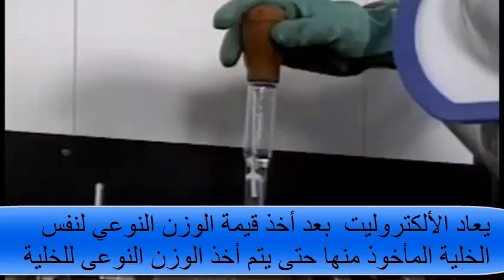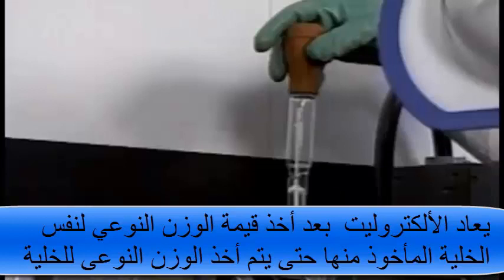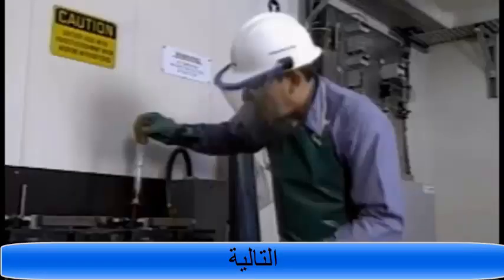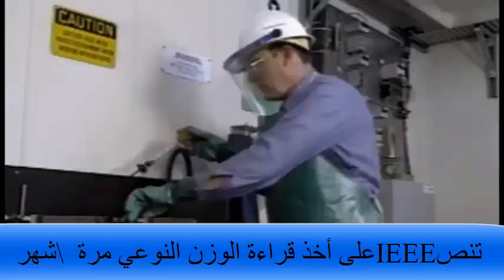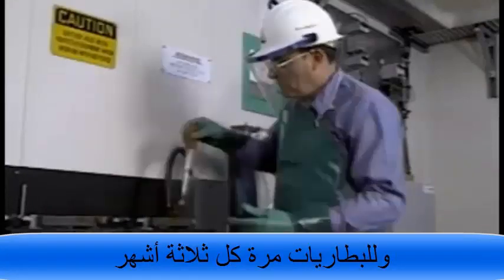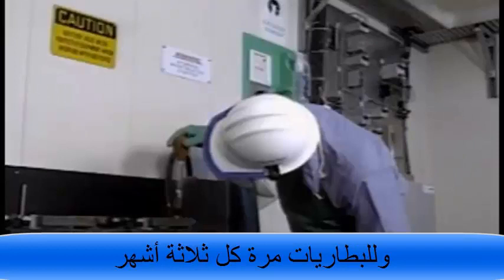After the specific gravity reading is taken, the electrolyte is returned to the same cell from which it was taken, and the specific gravity of the next cell can be taken. IEEE Standard 450 recommends checking pilot cell specific gravity once a month, and all cell specific gravities at least once per quarter.